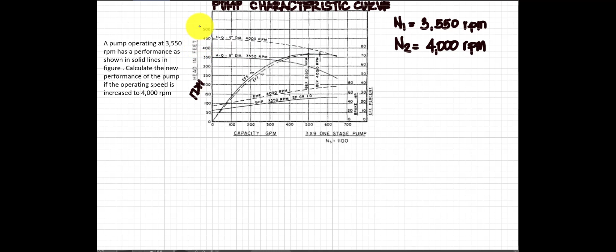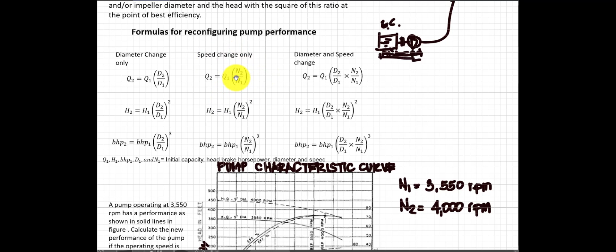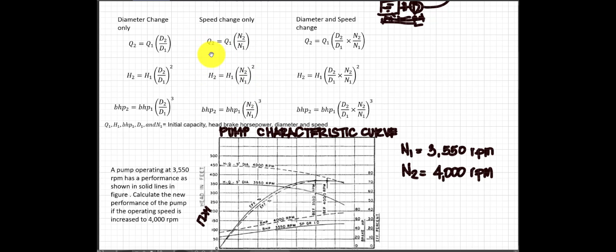Now, kung babalikan natin yung formulas for reconfiguring the pump performance. So, we change the RPM. So, speed change only. Okay, so you notice here, we have this ratio, corresponding ratios, no? So, we'll try to use this one to compute yung pagbabago ng flow rate, head, and brake horsepower. Okay. So, let's try to use yung correction factor.